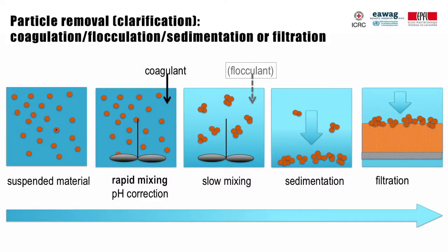Coagulation is usually a pretreatment step. Its goal is to change fine dispersed particles into larger agglomerates that can be removed by sedimentation or filtration or both. In the coagulation process, a metal salt such as aluminum or iron salts are added to water containing dispersed, negatively charged particles. Aluminum ions destabilize the particles by neutralizing their charge. Water is rapidly mixed and pH may need correction. These destabilized particles form flocs which grow larger during slow mixing and finally settle down and can be more easily filtered out.